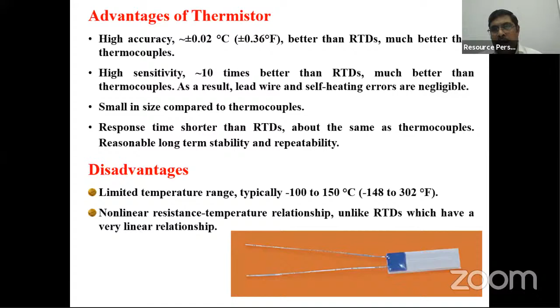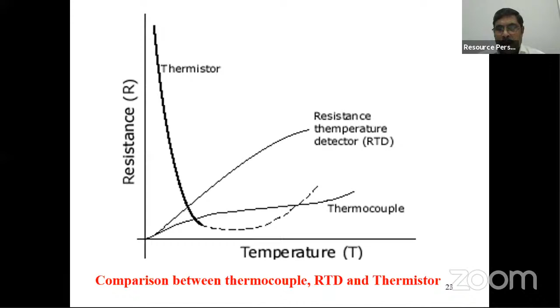So now here you can see a direct comparison between the thermistor, thermocouple, and RTD. The thermocouple also, with respect to temperature, has an increase in resistance. RTD has an almost linear relationship, whereas the thermistor is inversely proportional. But most of the thermistors do not have a linear relationship with temperature. Maybe to some range, it will be linear, and again, it will be flat, and then different. So therefore, according to your range, you have to select the thermistor.